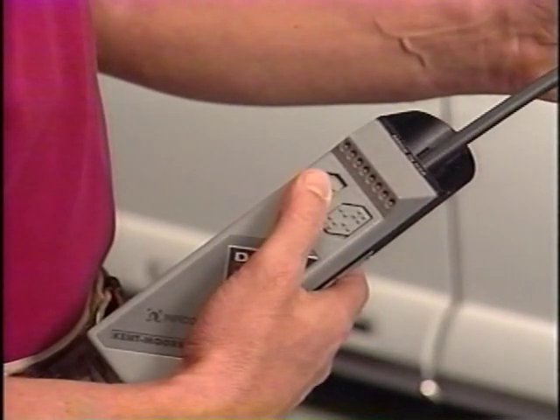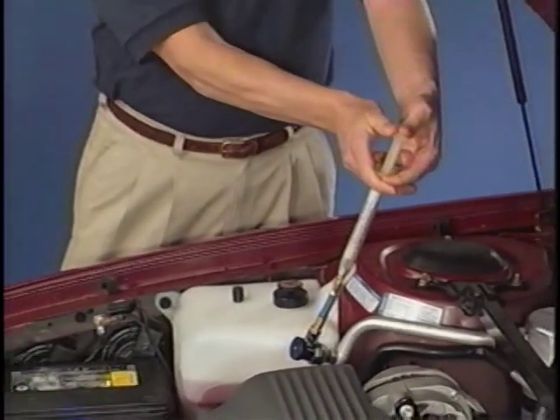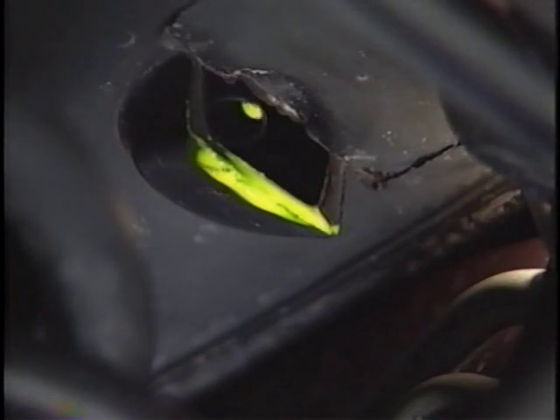You may recall in Know-How 207, I showed the battery-powered D-TEK electronic detector. The device offers a modern alternative for those who want the most advanced technology. I also demonstrated the use of the leak dye injector. The dye is particularly effective in tracing slow leaks that don't show up right away. Also, as Ed said, R134A leaks are more difficult to see as the light oil is often washed away by condensation.